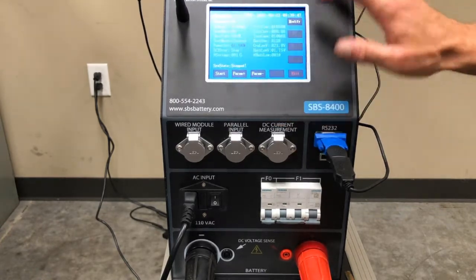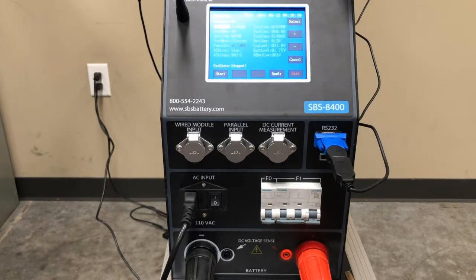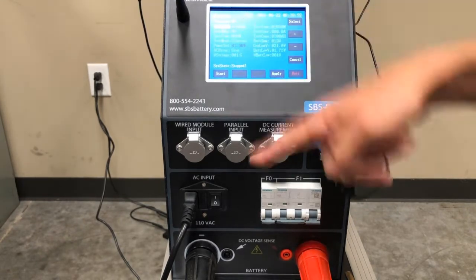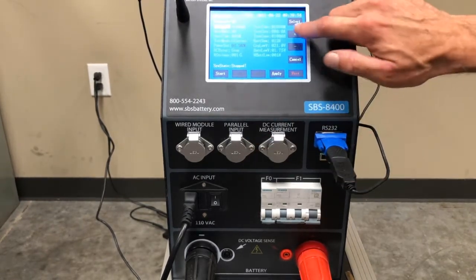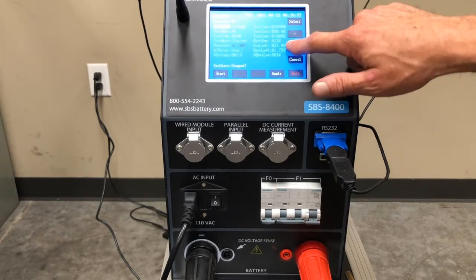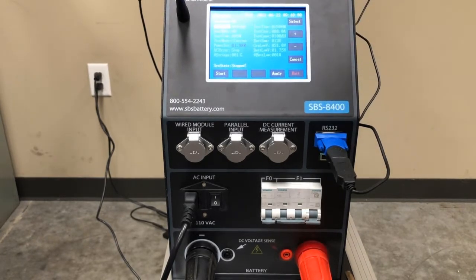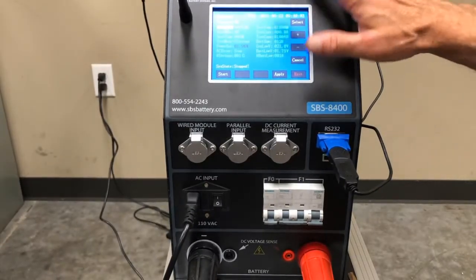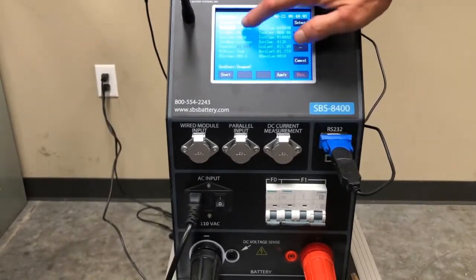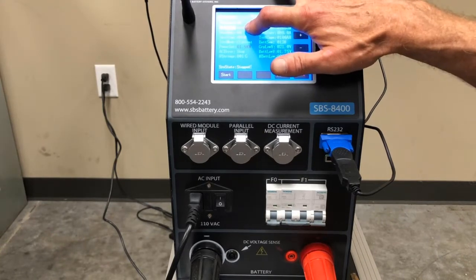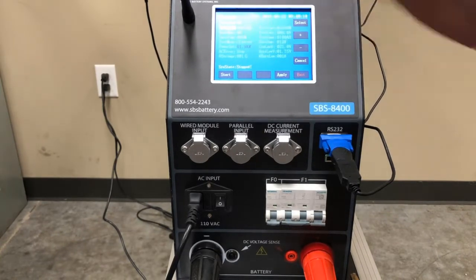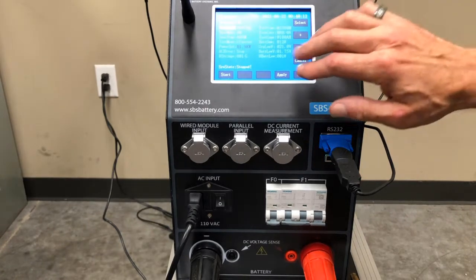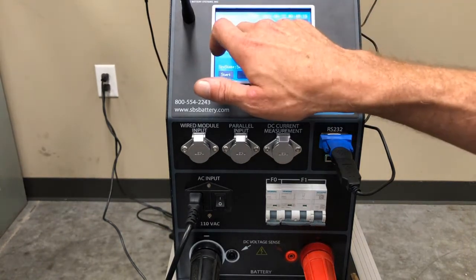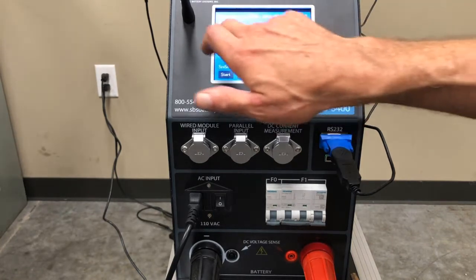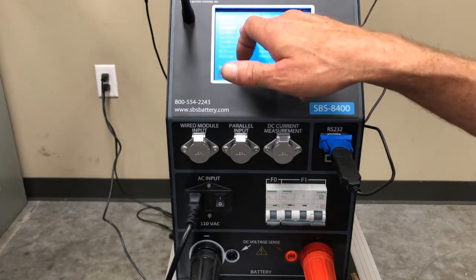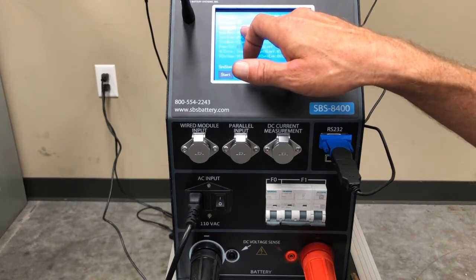So to modify any of the parameters, we're in a preset. We hit the modify key. Again, my select is my arrow key to choose which value I'm on. And then my plus and minus keys add or decrease from the value that's displayed on the screen. So my test, I'm running 97 amp hours. That's 1 hour, 97 amps is going to be 97 amp hours. Right. If it was 50 amps for 3 hours, my amp hour rate would be 150 amp hours, because that's the total that I'm pulling from the battery.